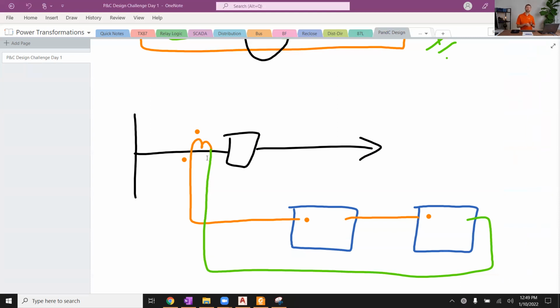We talked about breaker bushing CTs. This would be a dead tank circuit breaker that has bushing CTs. If it's a live tank circuit breaker, it would not have those. You'd have to have a standalone CT stand, but that's usually much higher transmission voltage classes. Typically, we have breaker bushing CTs. And so let's look at the other end of things.